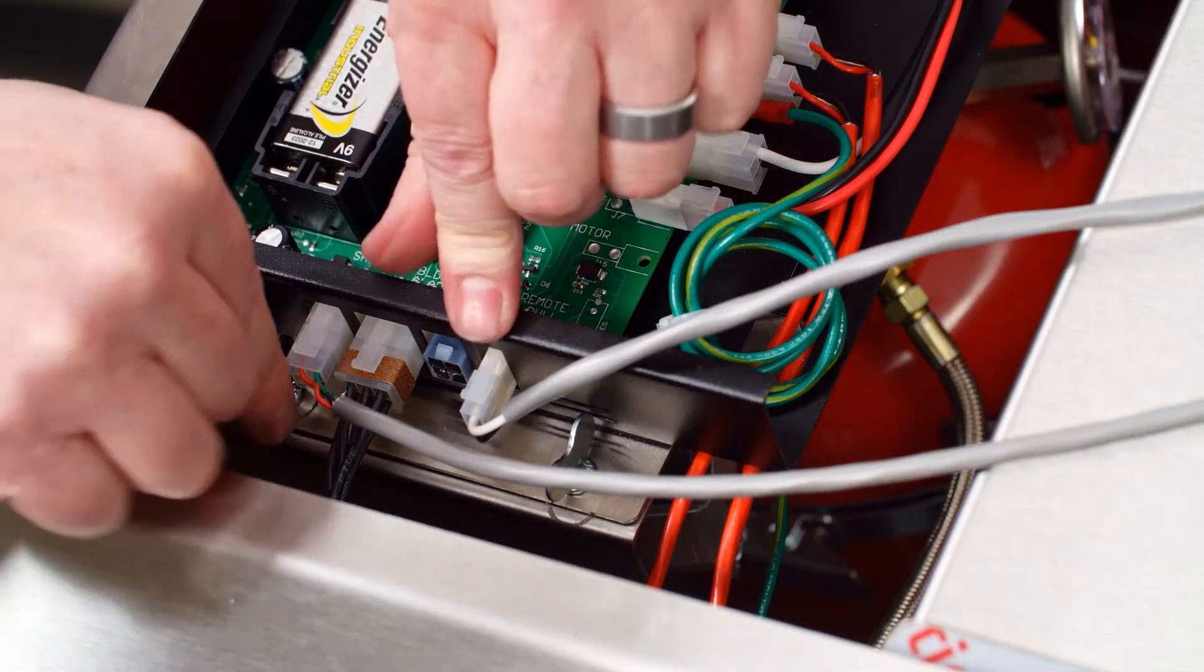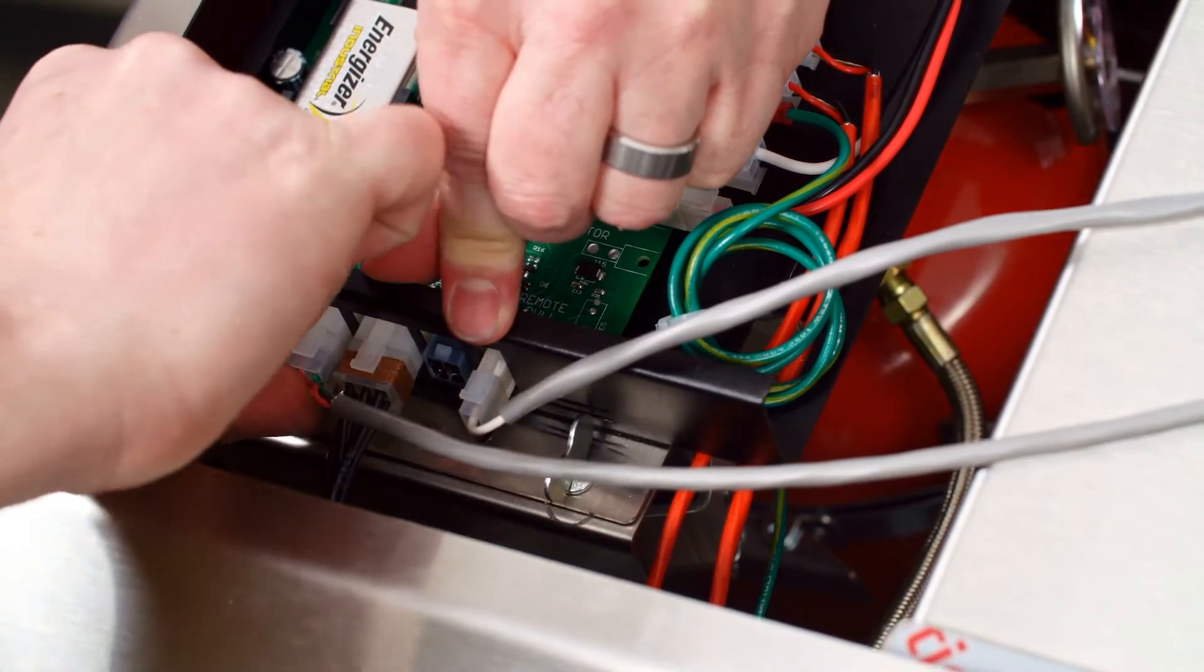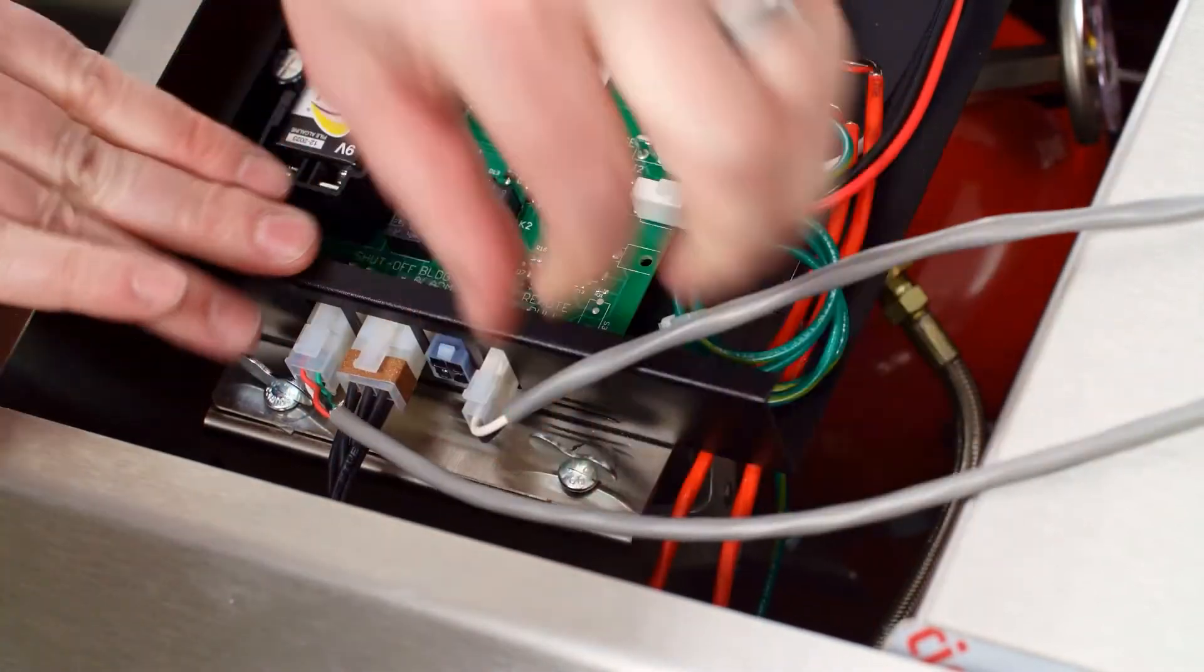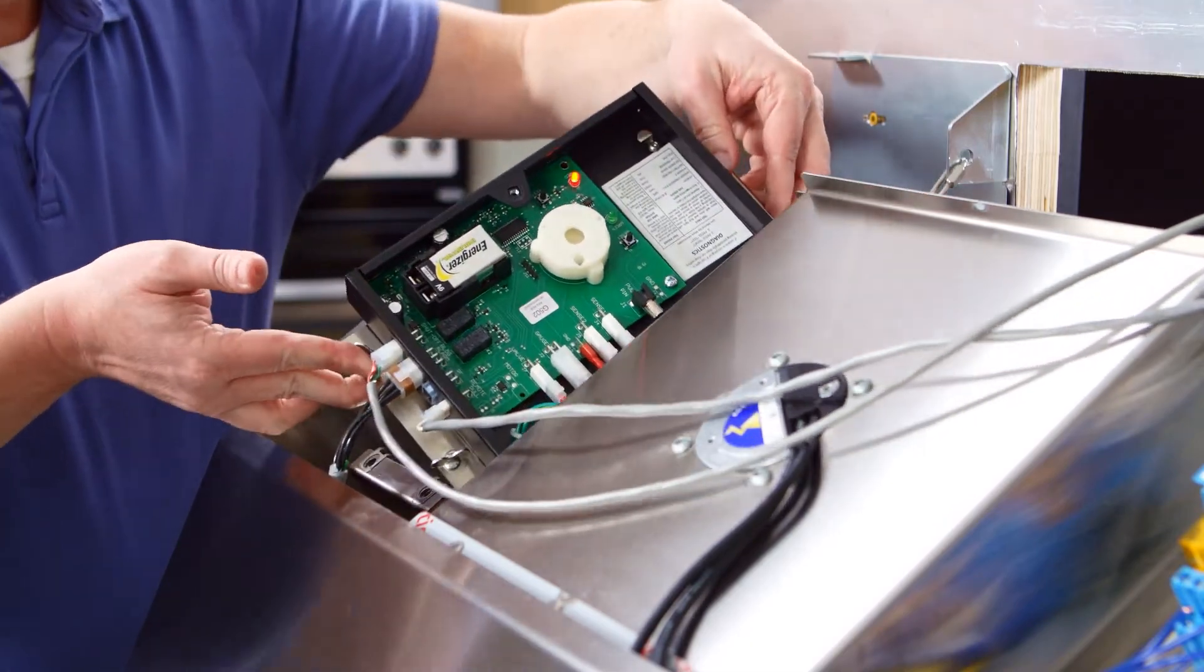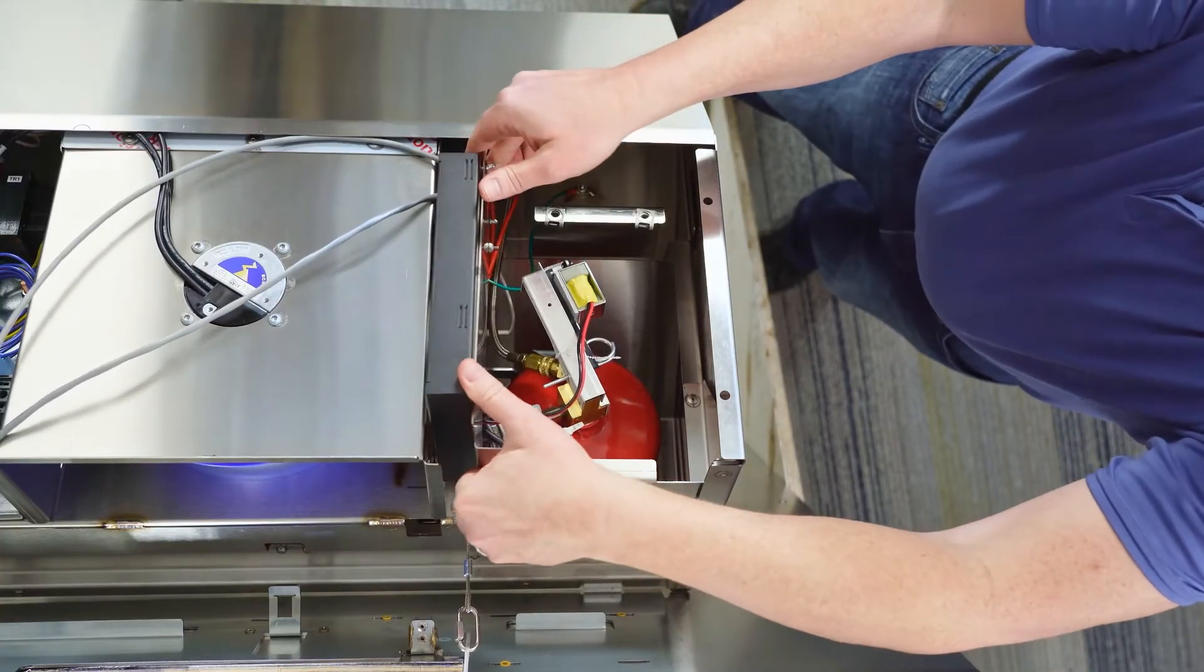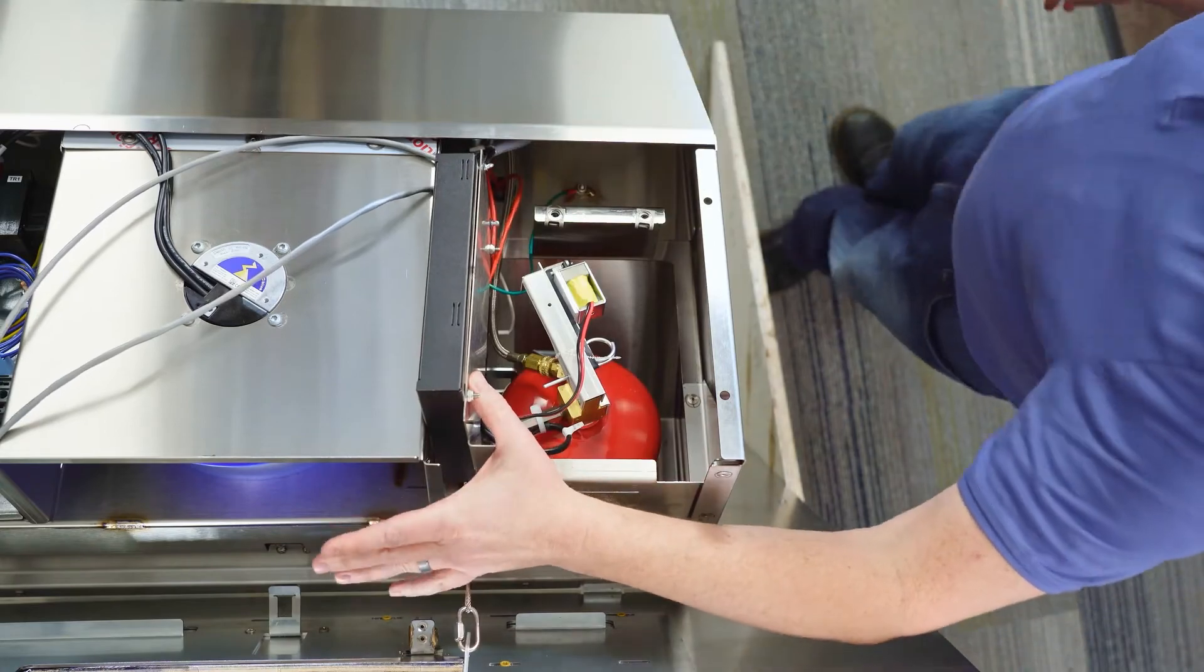Verify the disconnect is powered and all burners on the range are off. Remove the wing screws that hold the fire suppression board enclosure in place. Without disconnecting any cables, expose the agent tank by sliding the control board assembly towards the middle of the hood and down so it's next to the tank.